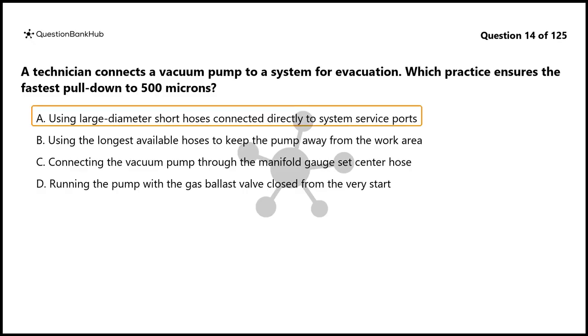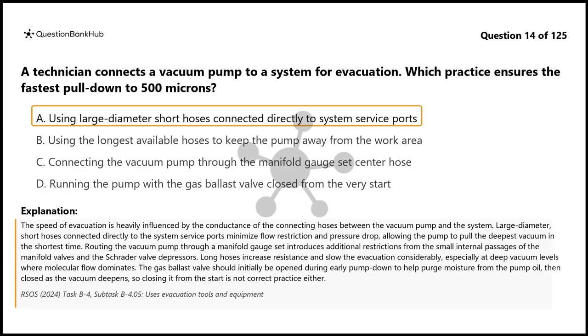The correct answer is A. The speed of evacuation is heavily influenced by the conductance of the connecting hoses between the vacuum pump and the system. Large diameter, short hoses connected directly to the system service ports minimize flow restriction and pressure drop, allowing the pump to pull the deepest vacuum in the shortest time.